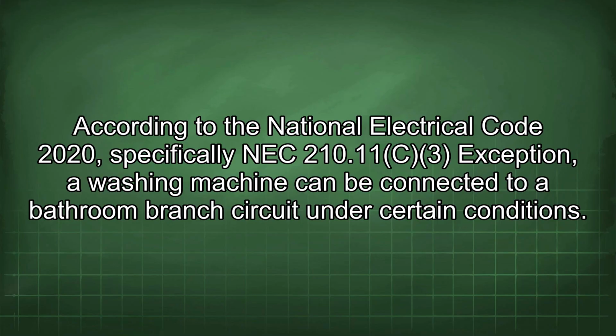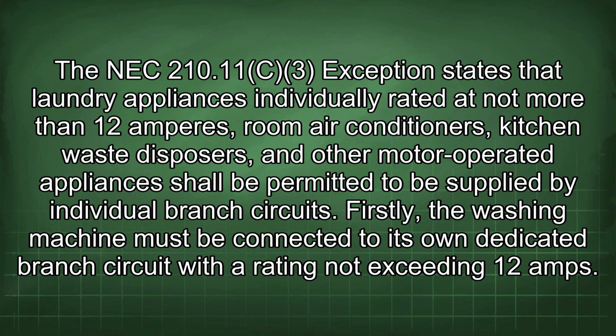According to the National Electrical Code 2020, specifically NEC 210.11c3 exception, a washing machine can be connected to a bathroom branch circuit under certain conditions. The NEC 210.11c3 exception states that laundry appliances individually rated at not more than 12 amperes, room air conditioners, kitchen waste disposers, and other motor-operated appliances shall be permitted to be supplied by individual branch circuits.